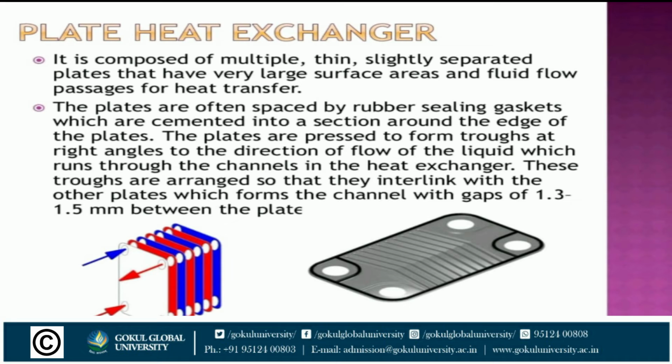Again, plate heat exchanger. It is composed of multiple thin, slightly separated plates that have very large surface area and fluid flow passage for heat transfer. As shown in the figure, the different plates are arranged in a plate heat exchanger. The plates are often spaced by rubber sealing gaskets which are cemented into a section around the edge of the plates. The plates are pressed to form troughs at right angles to the direction of flow of the liquid which runs through the channel in the heat exchanger.